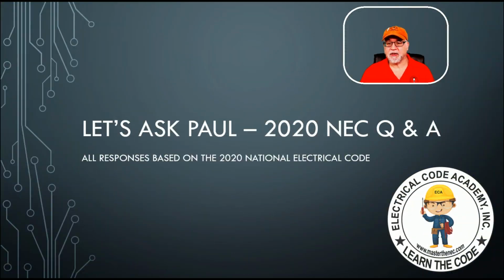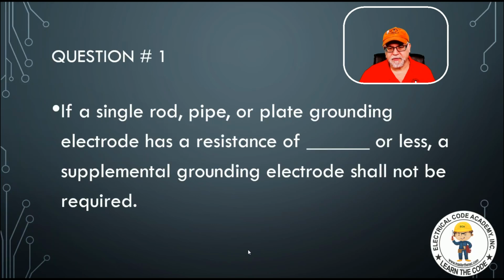All right, so let's go on and get into the program. Again, Let's Ask Paul. We're going to base it on the 2020 Q&A, and it's all based on our Fast Trax program, so we'll make sure we cover the information. The very first question I get asked is: if a single rod, pipe, or plate grounding electrode has a resistance of blank or less, a supplemental grounding electrode shall not be required.